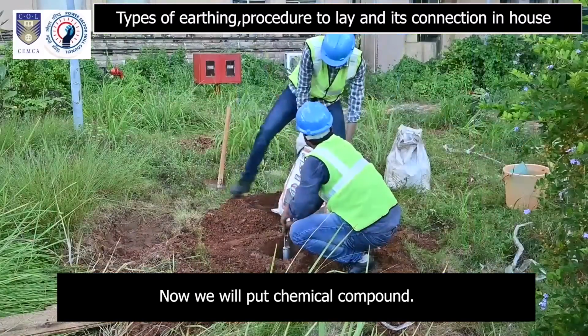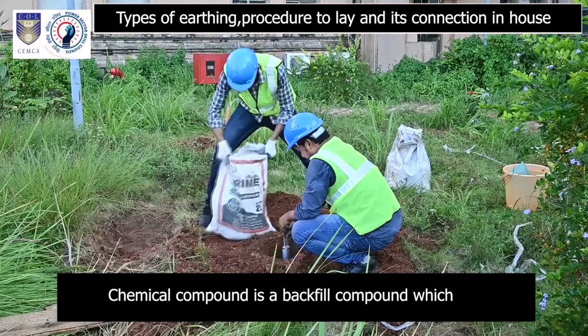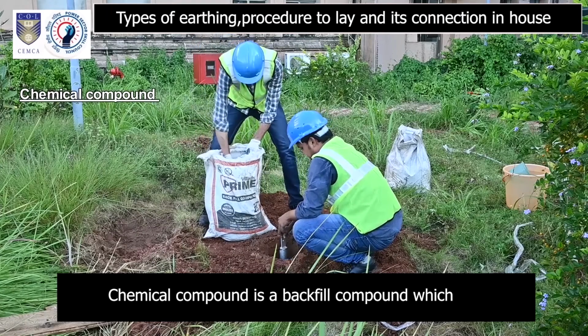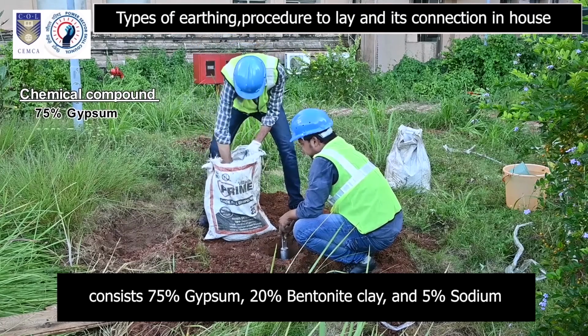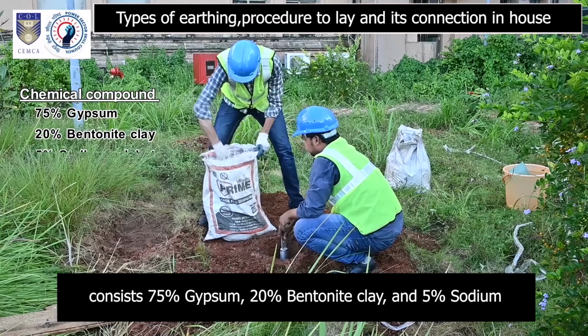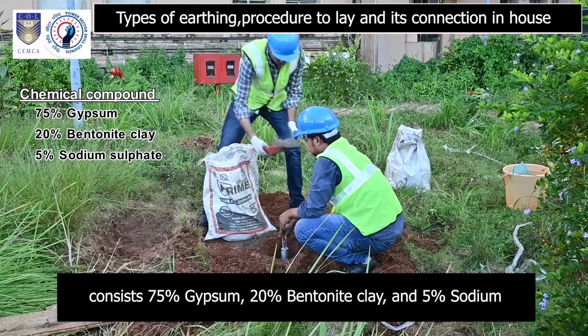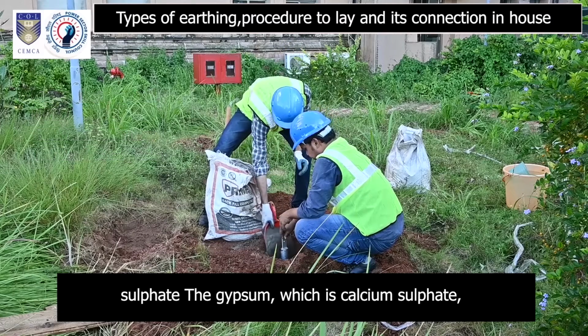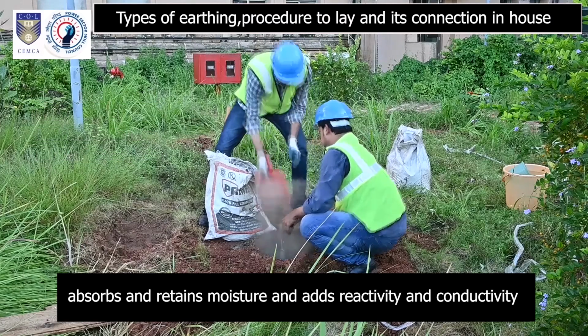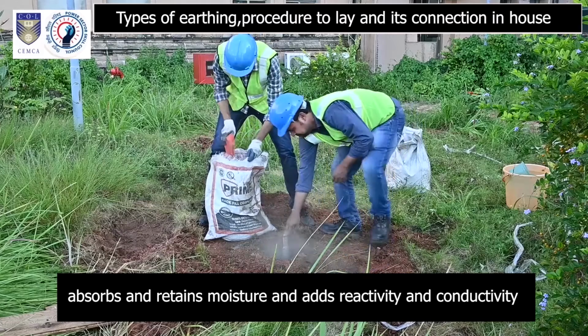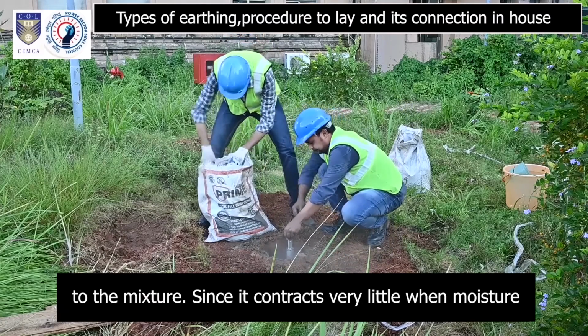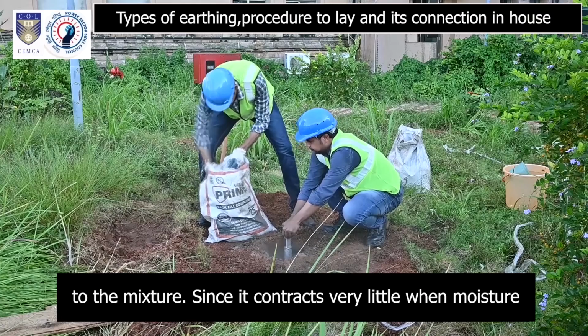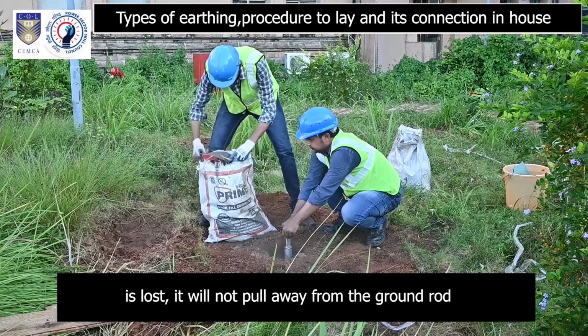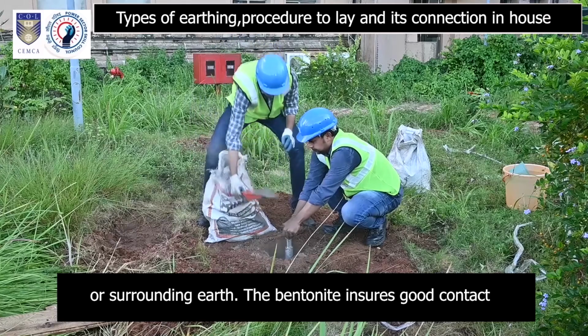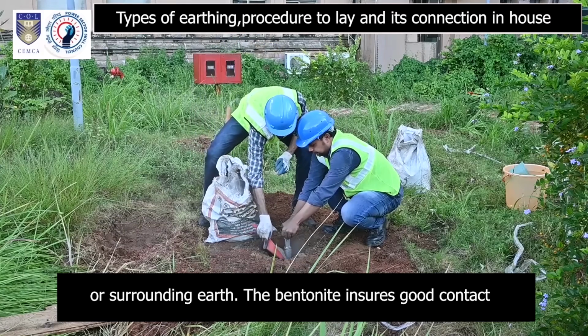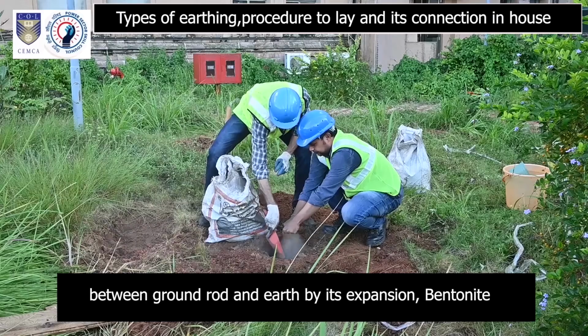Now we will put chemical compound. Chemical compound is a backfill compound which consists of 75% gypsum, 20% bentonite clay and 5% sodium sulfate. The gypsum, which is calcium sulfate, absorbs and retains moisture and adds reactivity and conductivity to the mixture. Since it contracts very little when moisture is lost, it will not pull away from the ground rod or surrounding earth. The bentonite ensures good contact between ground rod and earth by its expansion.